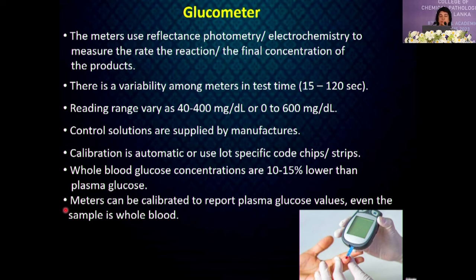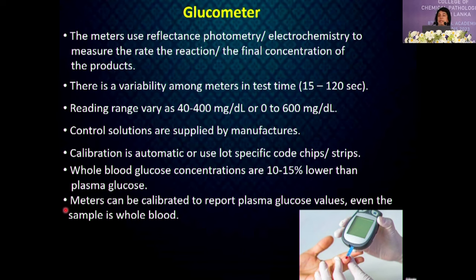Glucometers use reflectance photometry or electrochemistry to measure the rate of reaction or final concentration of product. Testing time and reading range vary between glucometers. The manufacturer provides a control solution, and calibration is automatic or uses lot-specific code chips or strips. Always remember that whole blood glucose concentration is 10 to 15% lower than plasma glucose, due to the water content of plasma being approximately 11% higher than whole blood. Glucometers can be calibrated to report plasma glucose values even when the sample is whole blood.